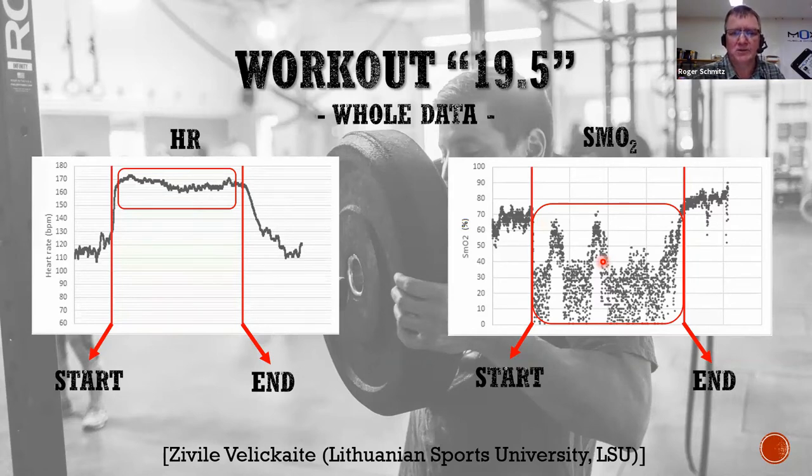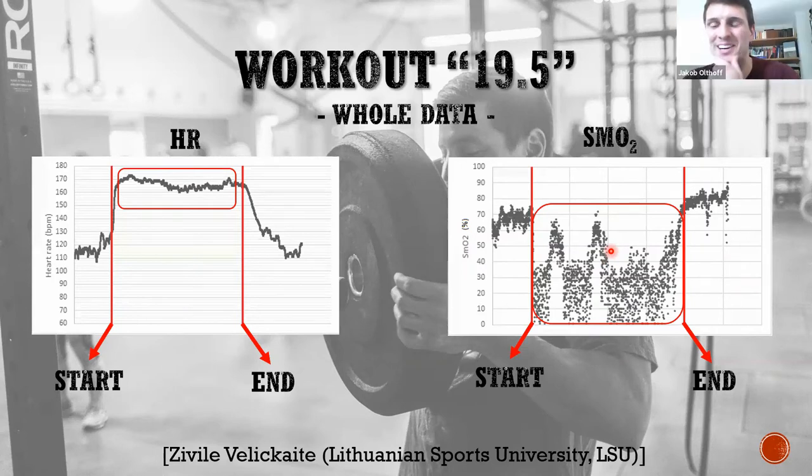Often we do get cleaner signals, and I'm guessing you were using the higher speed update rate in this mode. Yes, that is another factor in this data. It looks like the 2 hertz update rate was used, and normally the default update rate of the sensor is half a hertz, which would clean up a lot of that noise as well. Okay, I see. So the technological part is yours.